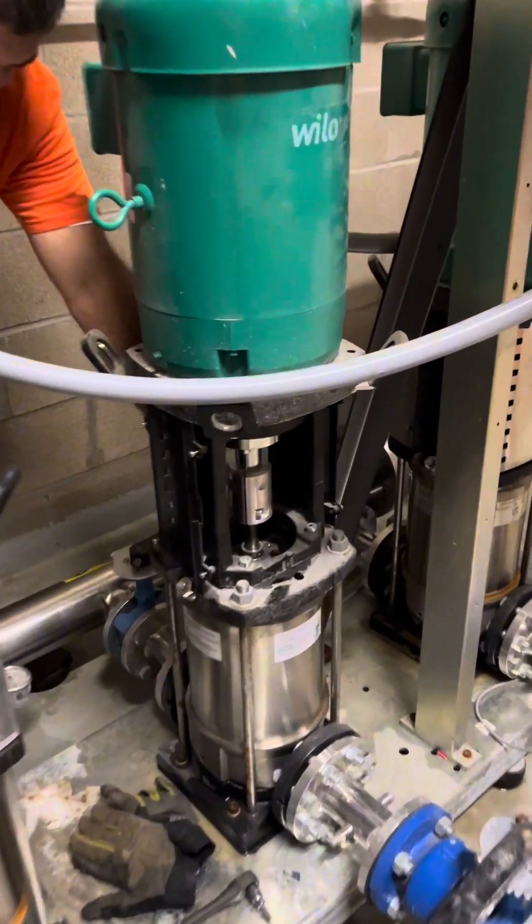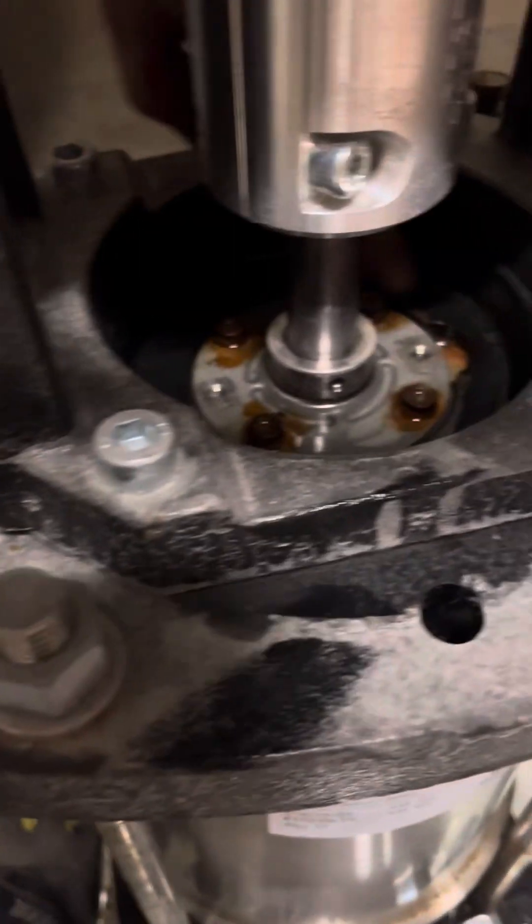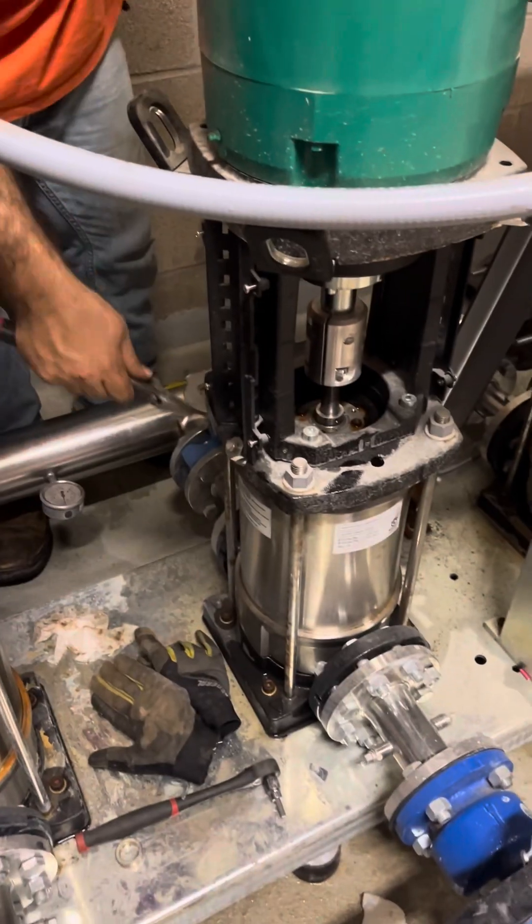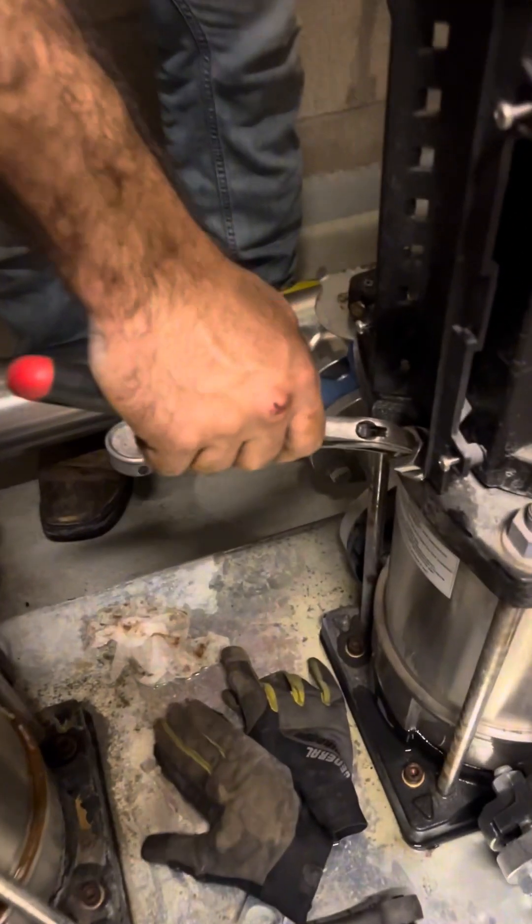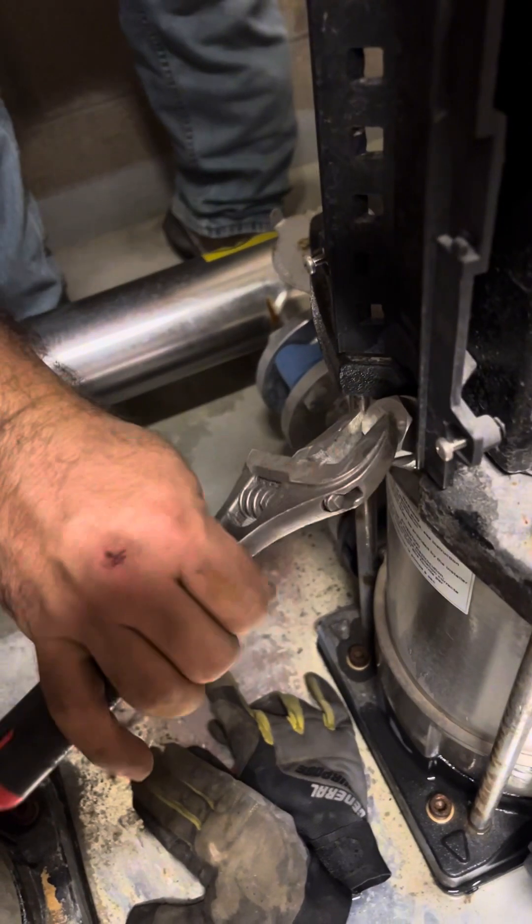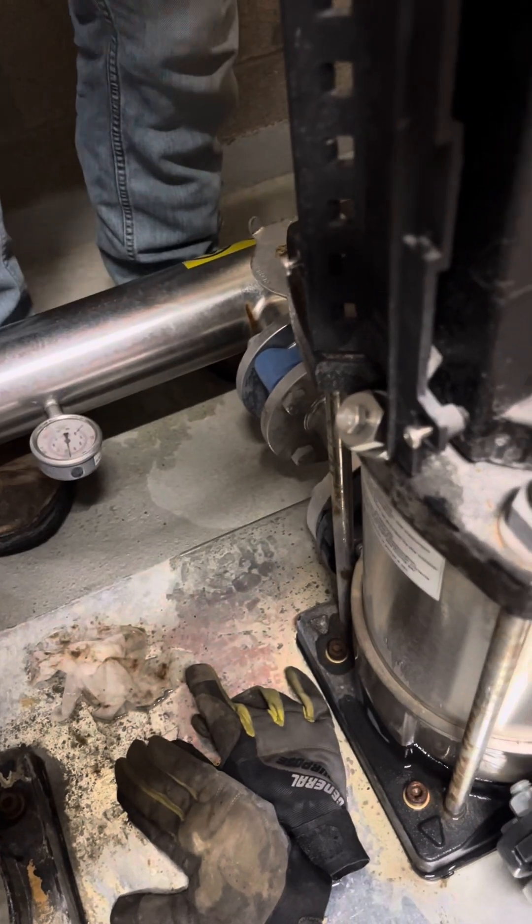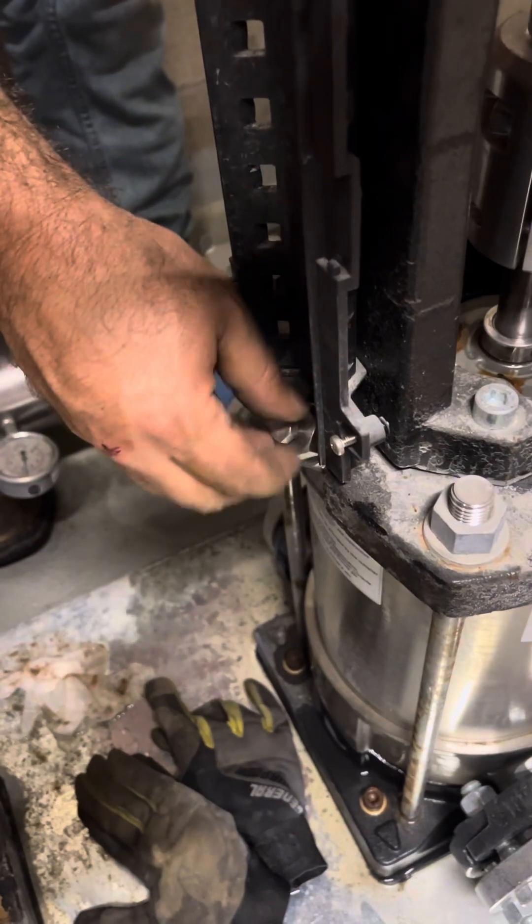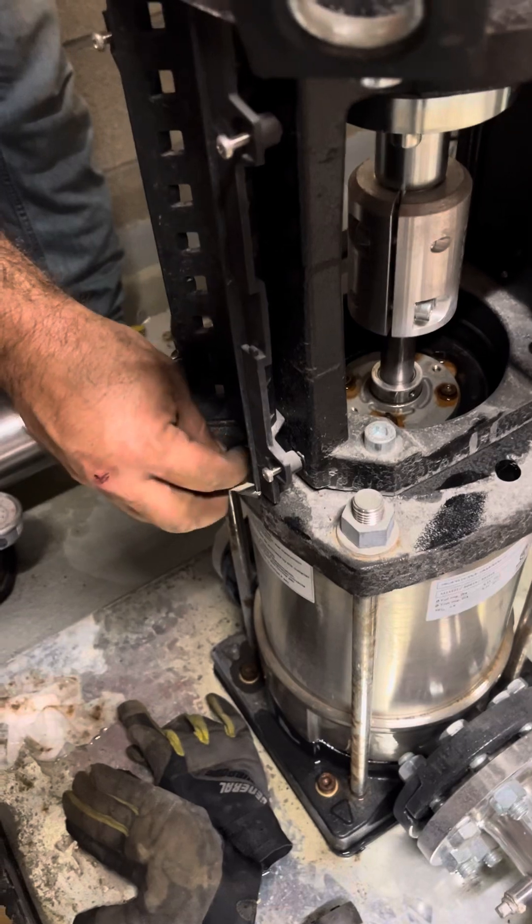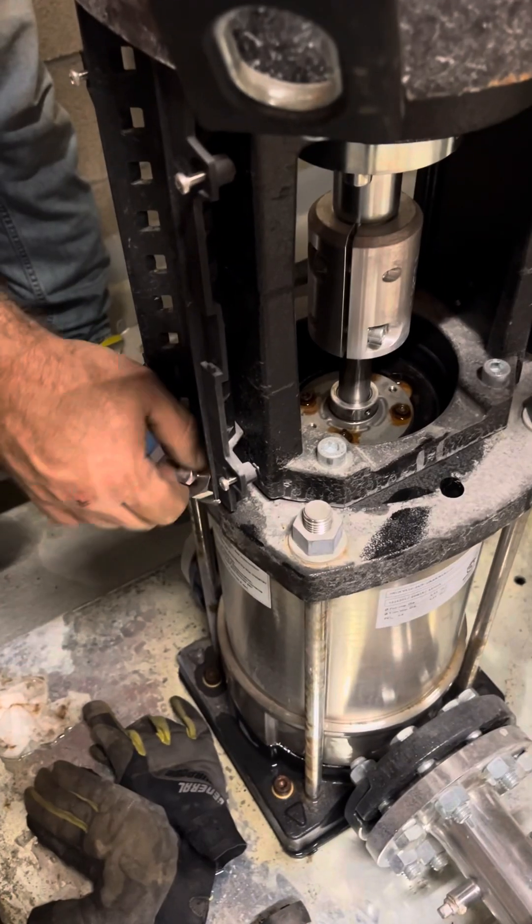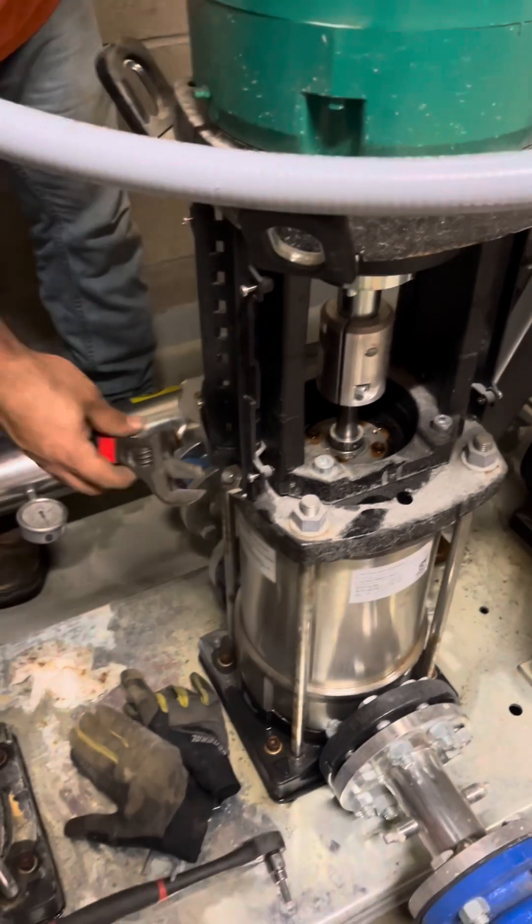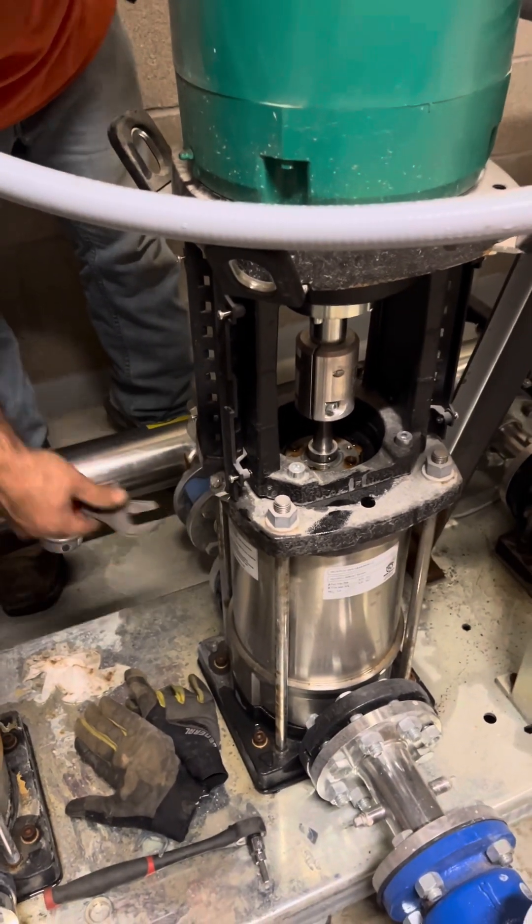If you take a look in here real quick, you can see from when it was leaking, it has a pretty good leak with water just constantly coming in there. This is an air relief valve that you can open up to relieve any water pressure that might still be trapped between these two iso valves. I'll take that all the way loose so I don't have to worry about water popping off while we're taking this apart, and I'll just snug that back up.